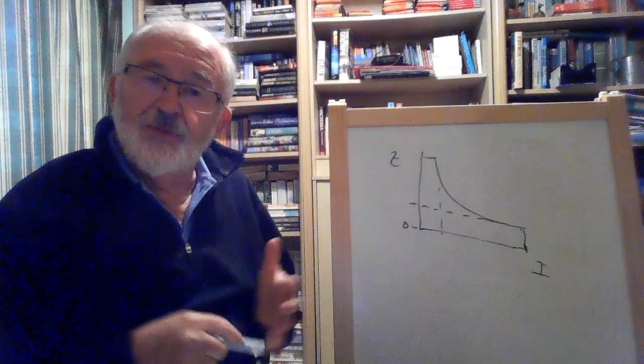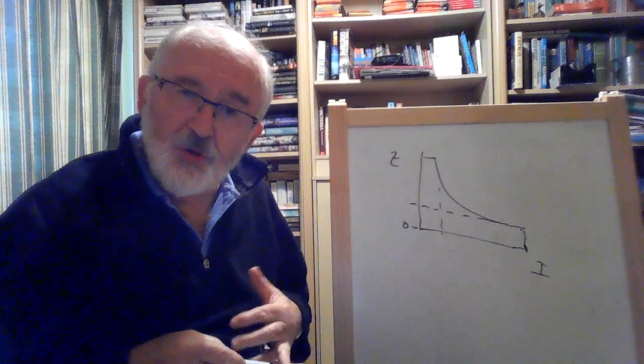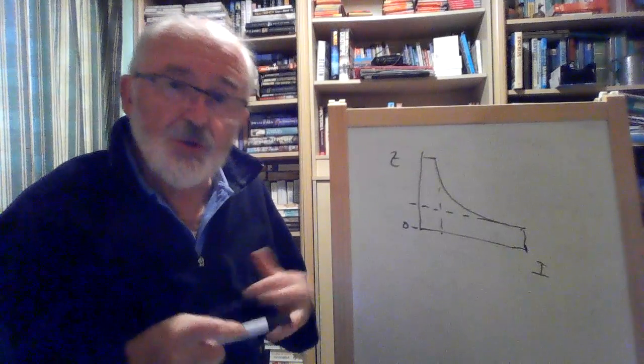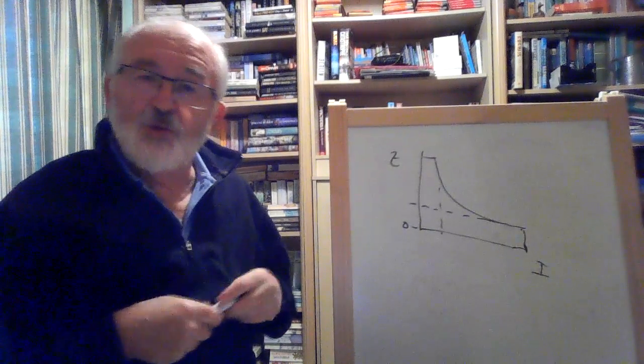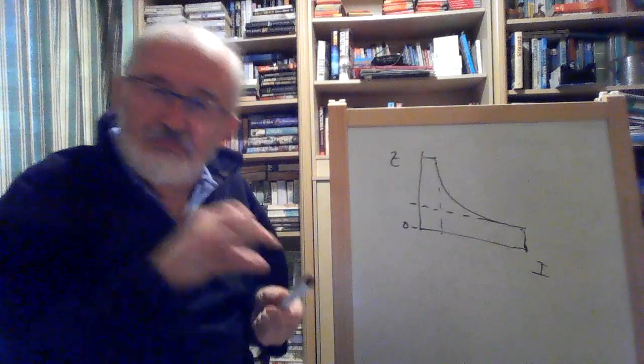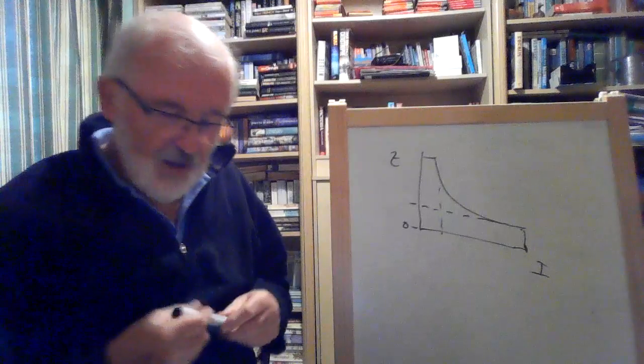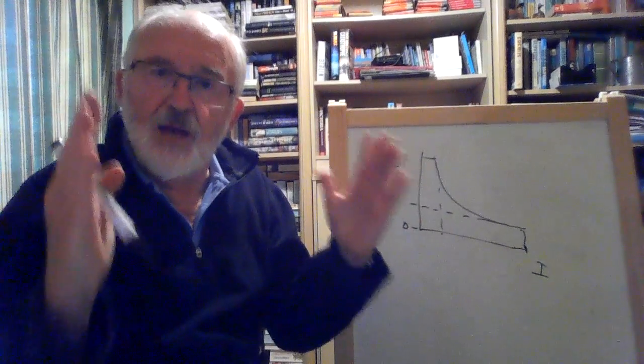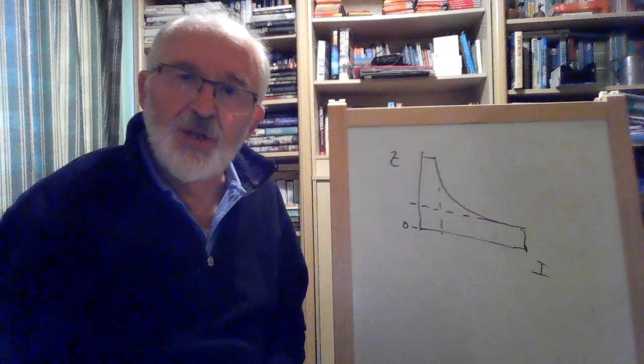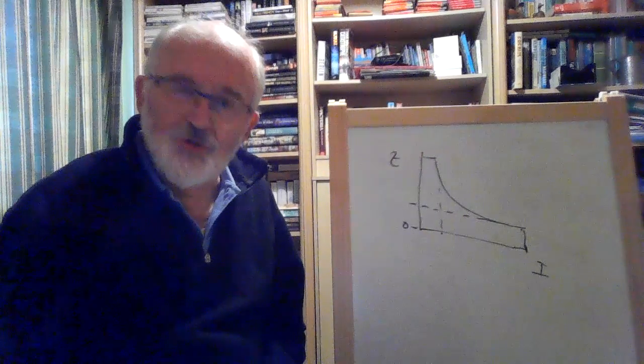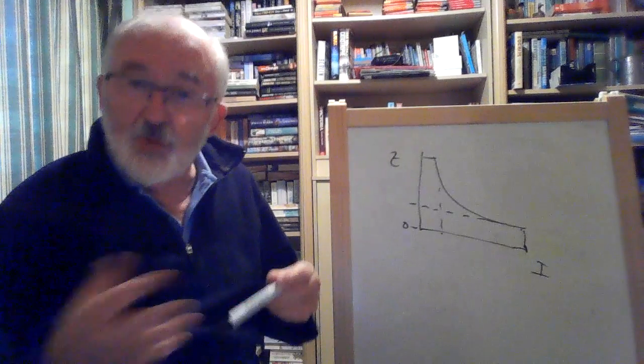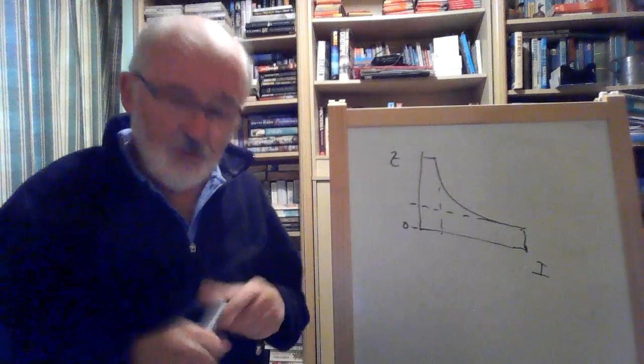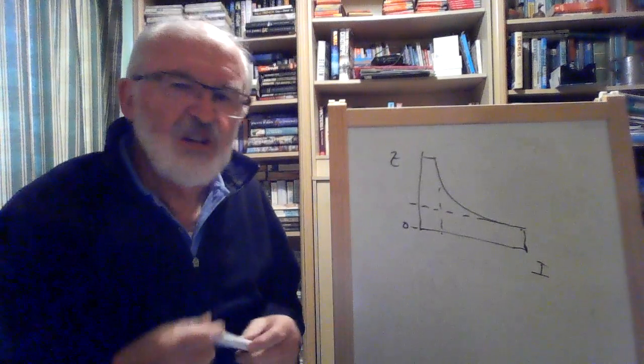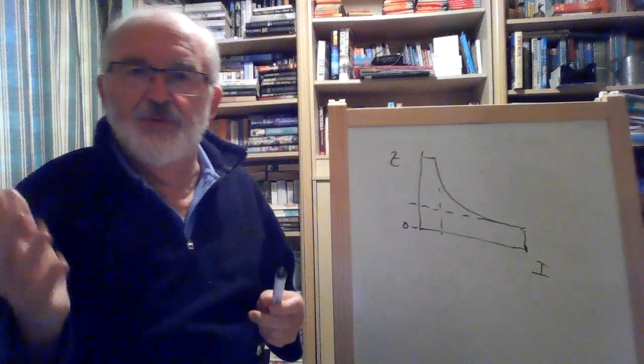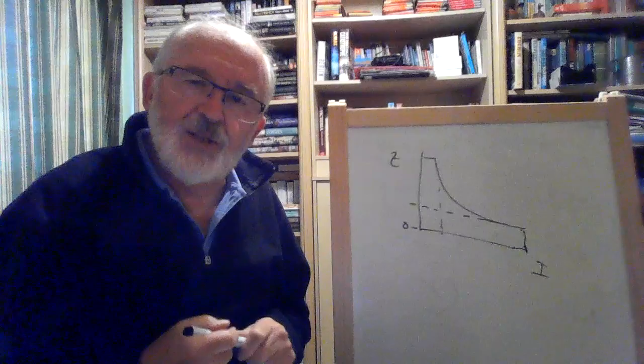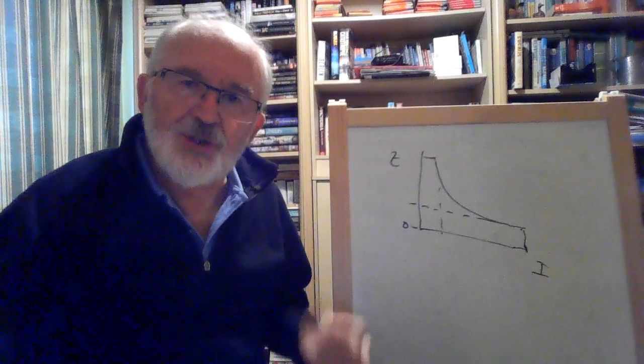Other protection devices we have on the generator, which are shown on the switchboard, are under voltage and over voltage, and those typical values are 80% of the line voltage up to about 120% of it. So if we go below or above those figures, then your under and over voltage trips will cut in. We also have under frequency and over frequency systems, and they're normally set approximately 4% above or below the stated frequency at which we're operating the system, 50 or 60 hertz, whatever it is.